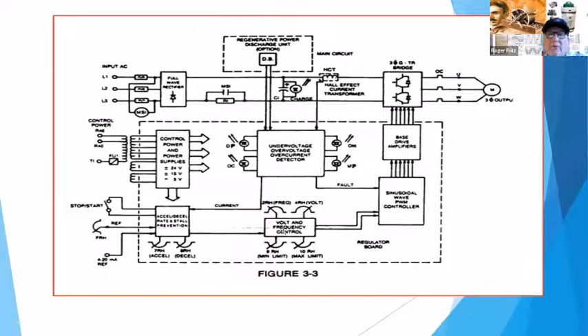So before the microprocessor, we had to do it the old way. It was all analog potentiometers. So we actually had to take voltage readings and power readings constantly. And these are all here, little dial potentiometers that were inside. You had a little screwdriver in there to basically control the firing processor, to the controller.